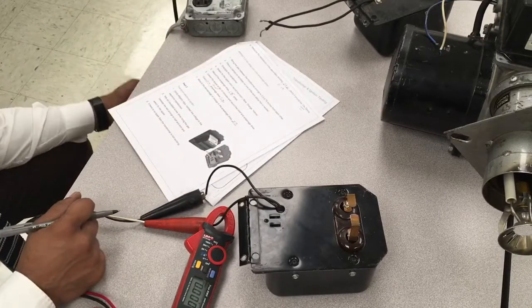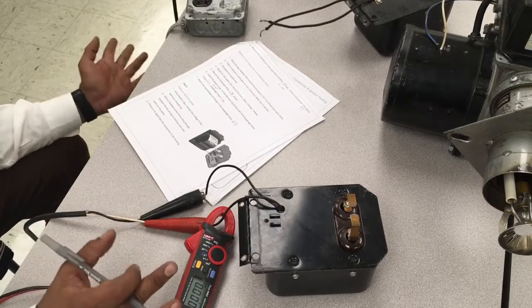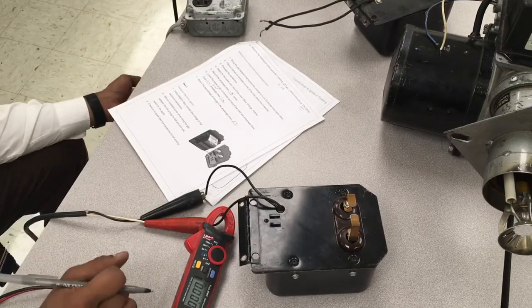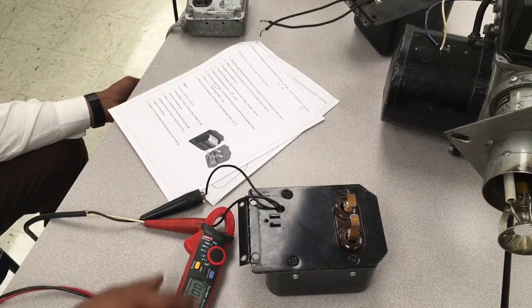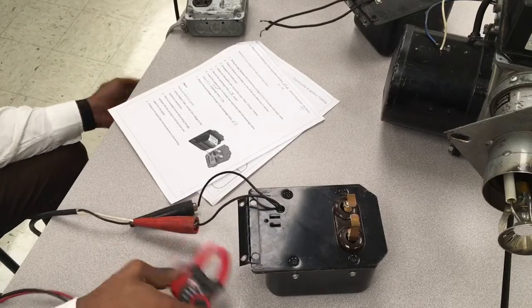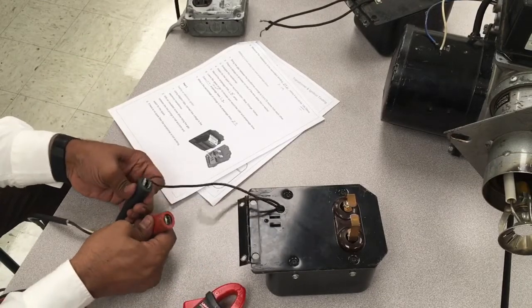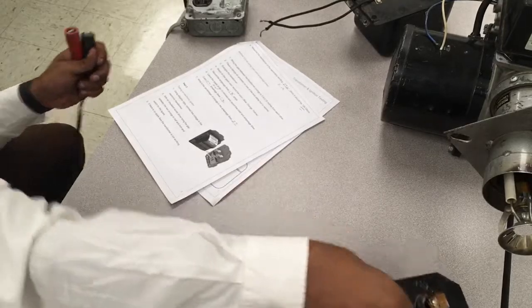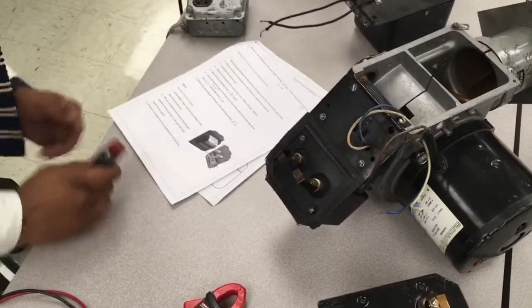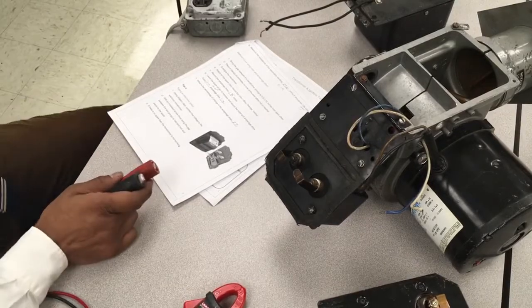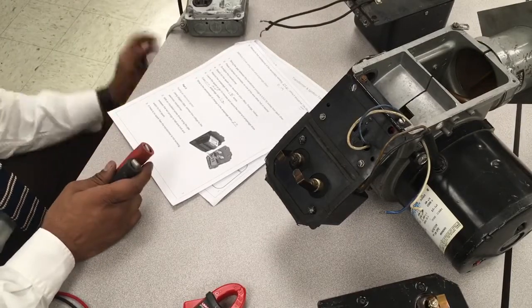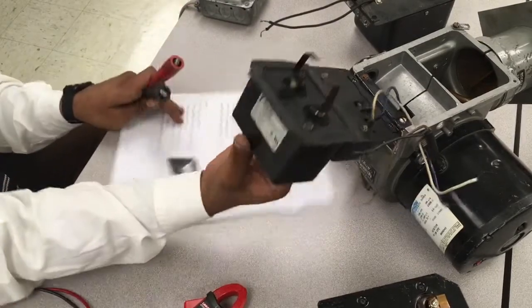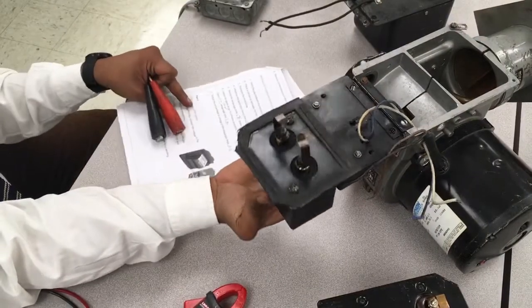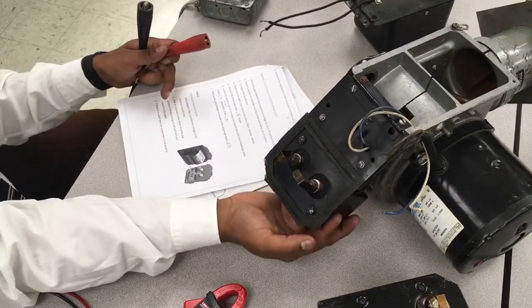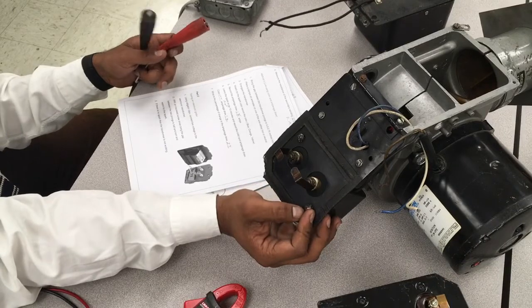So these are the 3 ways to test the transformer. Again, if I leave it for 10 minutes and you see a lot of fluctuation, you know that this transformer is weak and needs to be changed. And this is how we test a wound-up transformer. So how do we test the electronic one? So the electronic ones, they're either on or off. They have an integrated circuit inside with solid state, so it does not really change resistance.